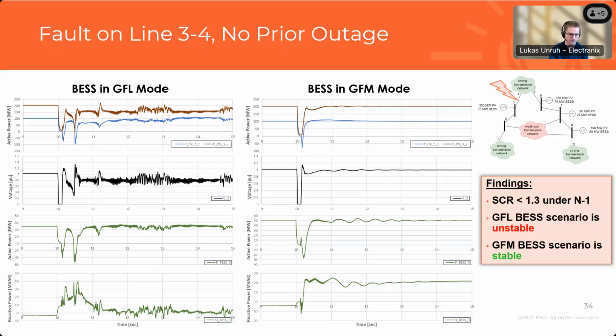Eventually they do stabilize, but the voltage is low and there's big oscillation, so that's a clear fail. And then on the right, we changed all the batteries in the system to grid forming, but really just that 75 megawatt would have been the one that made the big difference here to stabilize this case. So this is an example where changing that plant from grid following to grid forming would avoid the need for other mitigation like transmission or synchronous condensers at that location.